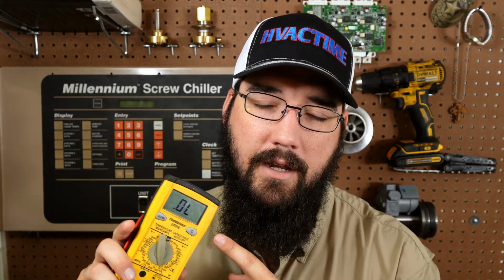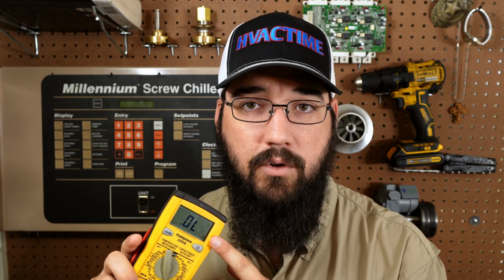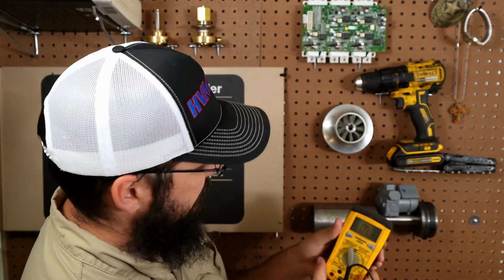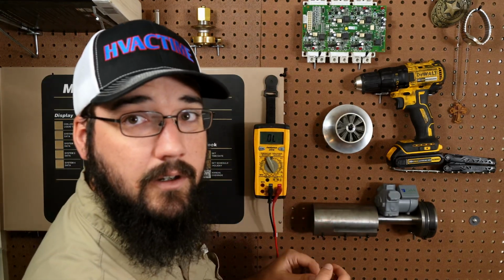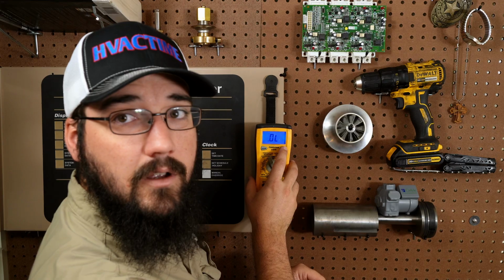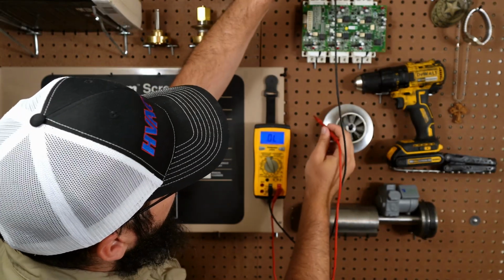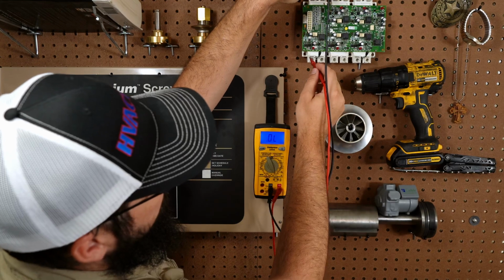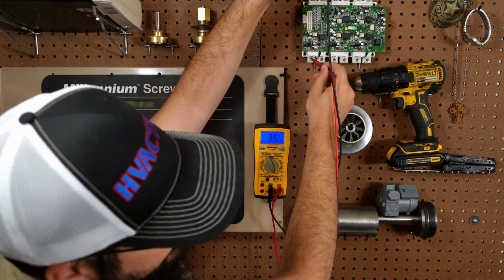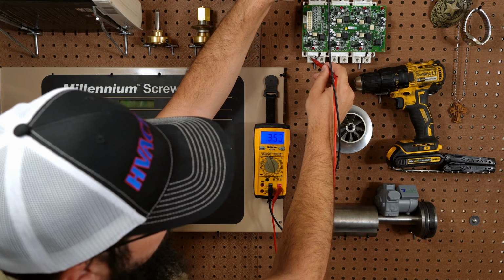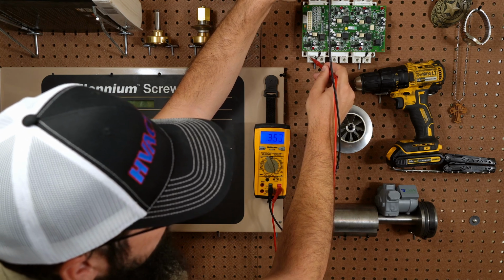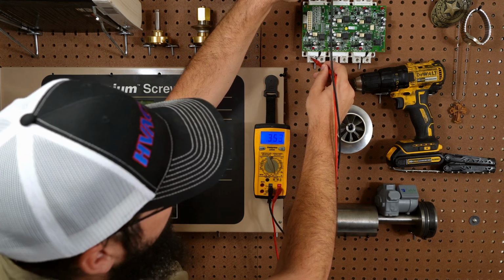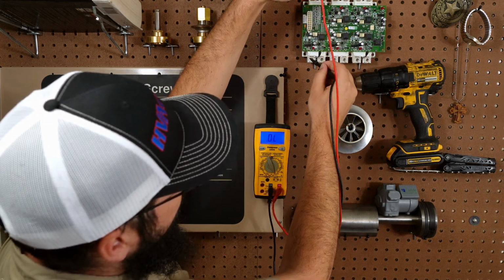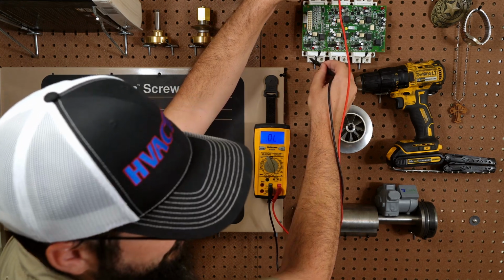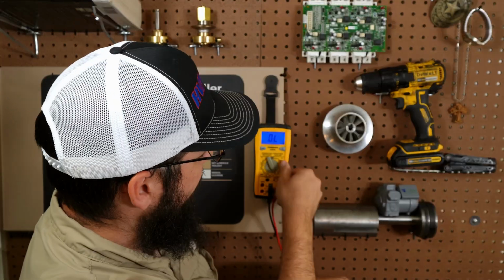What'll happen is this meter will generate a voltage value, a DC voltage. So if I use my little test I got here, we'll put that there. Maybe you can see that. If I go from one side to the other with my leads, I get a voltage of 0.35. And if I flip my leads around, I get an OL. That's a good test.